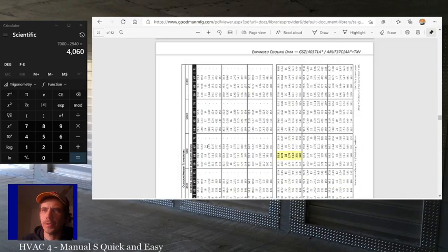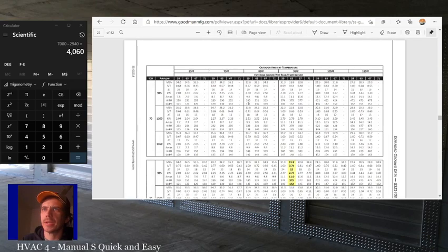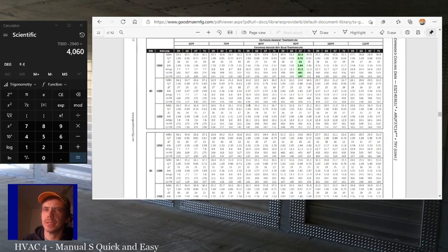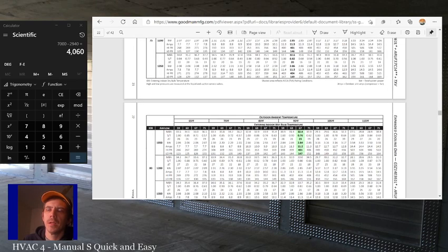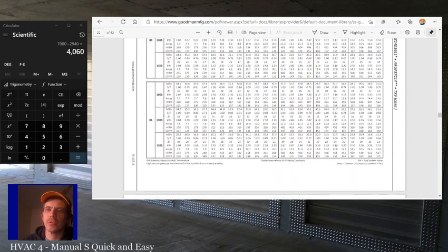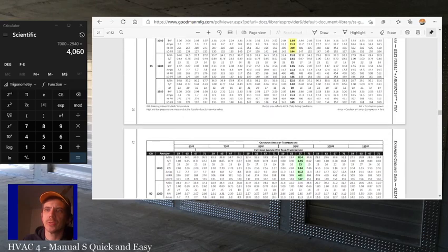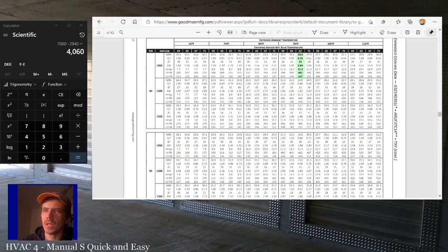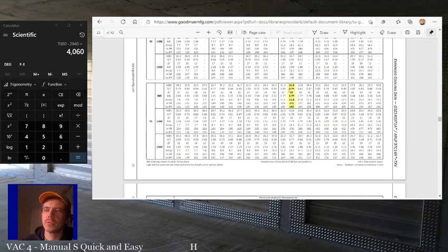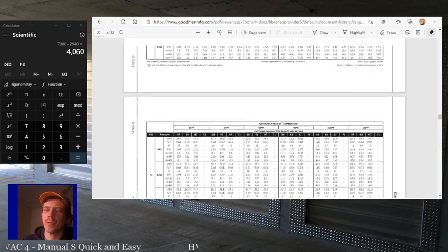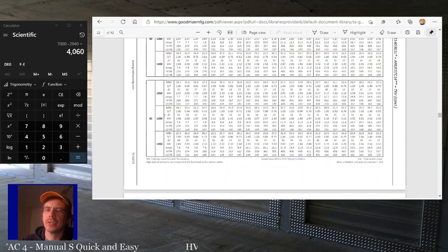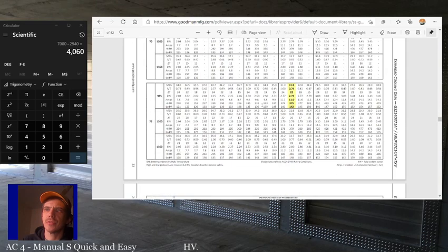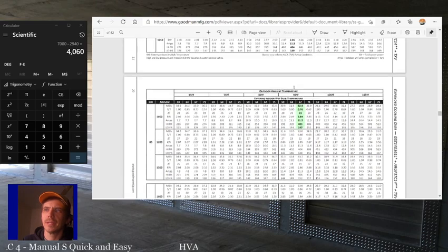One important note is if you're looking at this product data, you're usually going to have a couple things, and this is how Goodman points it out. You're going to have these indoor dry bulb temperatures and these outdoor temperatures, right? And then with Goodman, they've got this at 67 degrees wet bulb, right? And then they have this one, which is at 63 degrees wet bulb. This one is 80 degrees outside. This one is 75 degrees outside. So they've highlighted this here, and then they've highlighted this here.